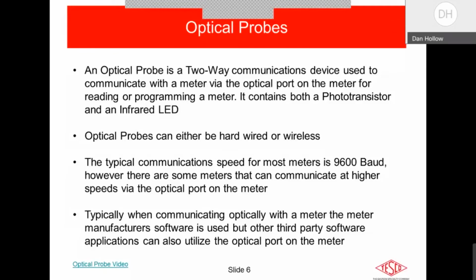And when we talk about data from the meter, what we're typically extracting when you read a meter optically with the meter manufacturer software is basically everything that meter is capable of storing. That would be all the stored registers, whether they're cumulative registers, instantaneous registers, demand, voltages, currents, all the types of registers that are programmed into that meter, as well as interval data, load profile data. Those words are synonymous. And also things like the history buffer, sometimes called an event log as well.